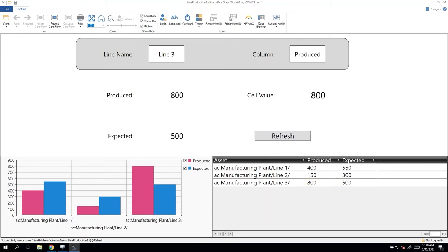As you can see, there's no limit to how you can modify a point name in runtime using this feature. And the values do not just have to come from user entry. You can use values from any tag that Iconics can read. You can modify a point name using values from OPC UA tags, Modbus, BACnet, SNMP, even other databases. You can have a database table full of point names and request their runtime values as data sources to create a display that's populated entirely by lists of points in a database. And none of this requires any scripting whatsoever.